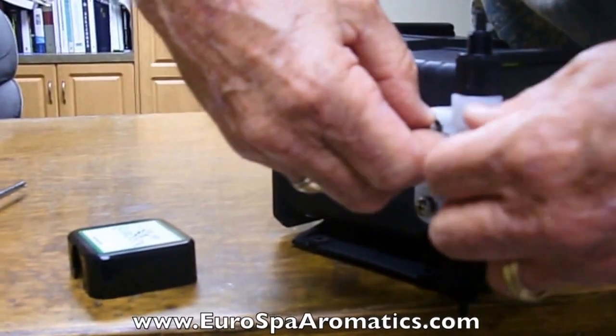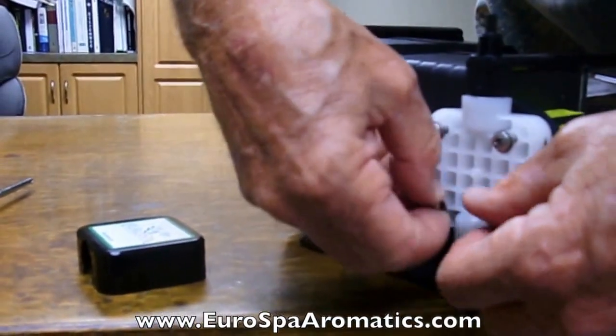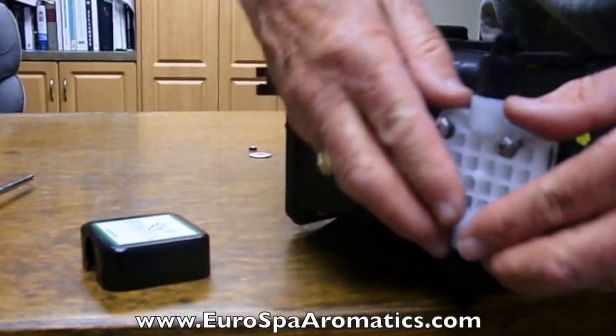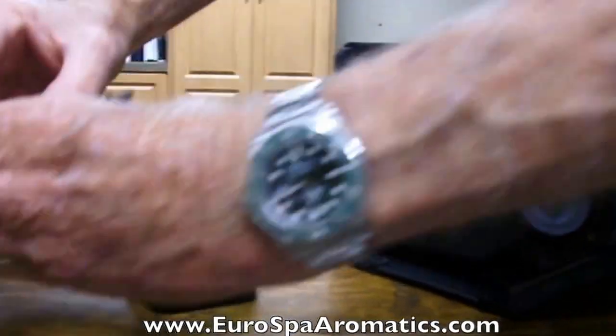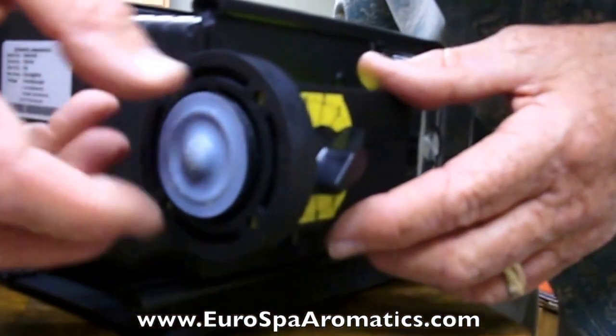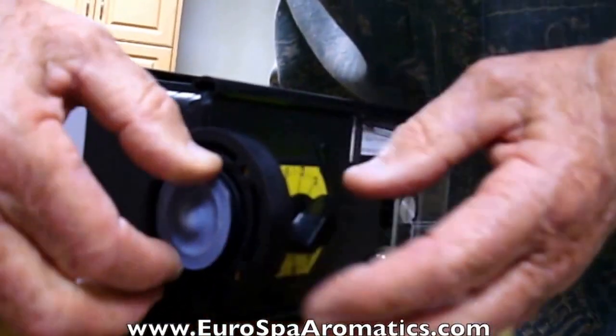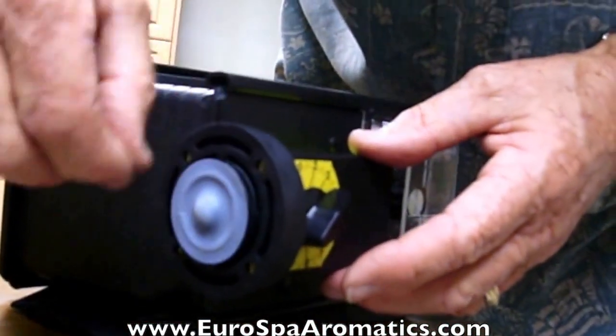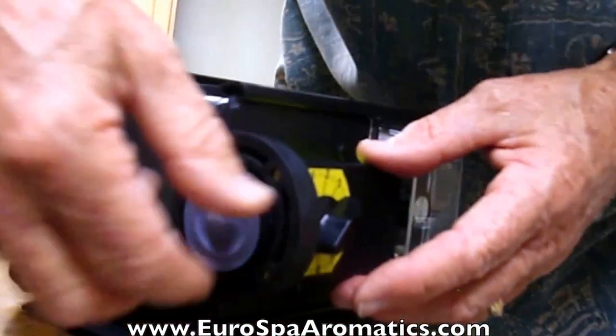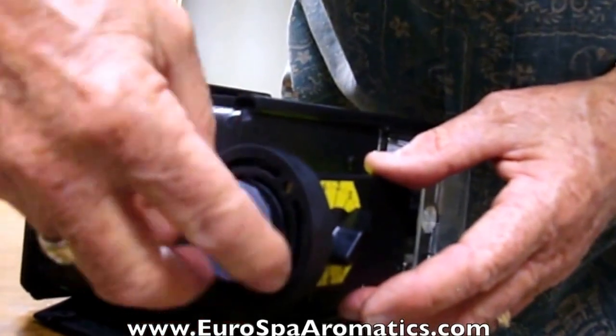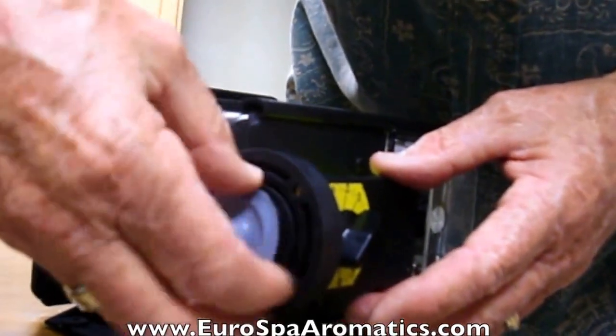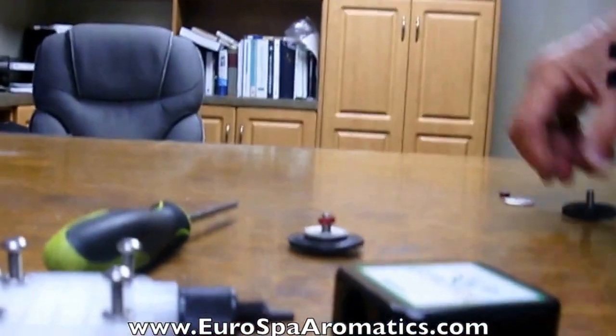It's not important at that point, but you do want to keep an even pressure so you don't warp the pump head. Off it goes, and here is now your diaphragm. The diaphragm will unthread, in most cases just by hand, but you may need to use a pair of pliers to start it. It unthreads in a counterclockwise manner and simply comes out of the shaft that controls the pump.